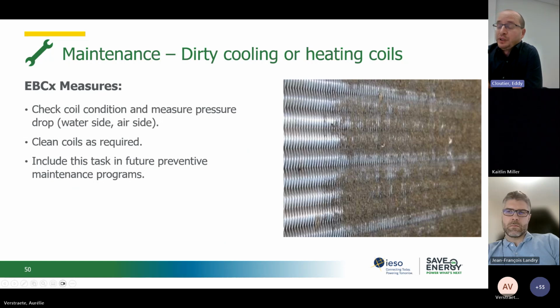So in that case, it's a really easy measure. Check coil condition and measure pressure drop to confirm that the problem is really a dirty coil. Well, in that case, it's quite easy to see in the picture. Clean coils as required, and of course include this task in the future preventive maintenance program.